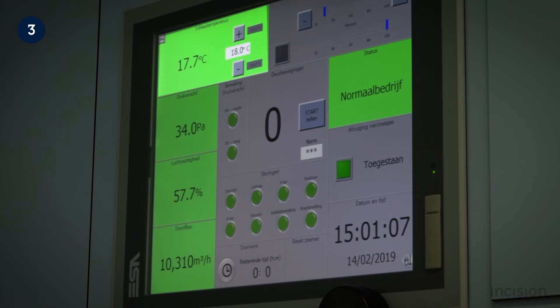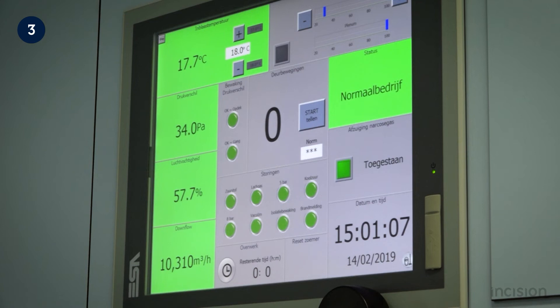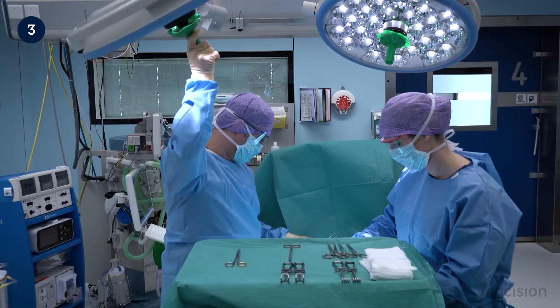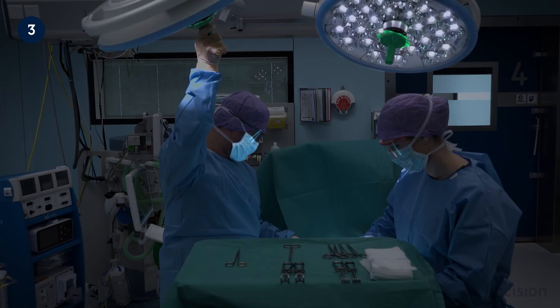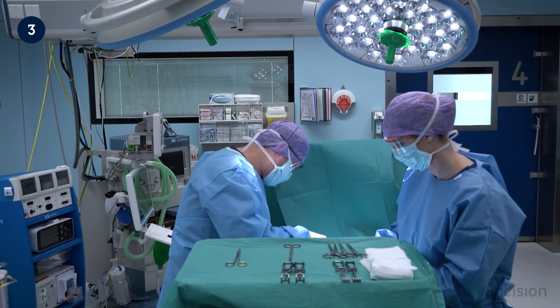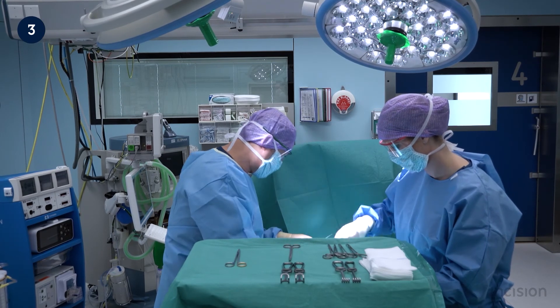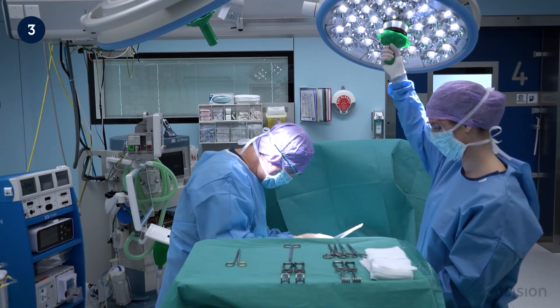The temperature within an operating room should be kept between 18 and 20 degrees Celsius (66 to 68 degrees Fahrenheit), with humidity between 30 and 60 percent. Supplied filtered air is usually around 19 degrees but can be adjusted if necessary; for example, higher temperatures are preferred for children since children's body heat decreases more quickly. Working in a cool environment reduces the chance of the sterile team being affected by heat caused by gowns, gloves, masks, and operating lights, as a sweaty forehead endangers sterility when sweat droplets fall into the sterile area.